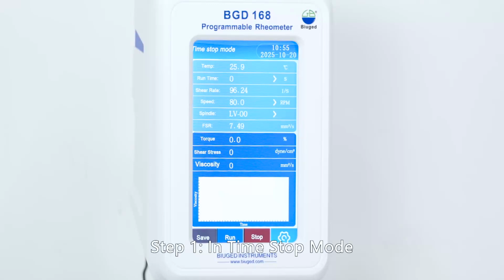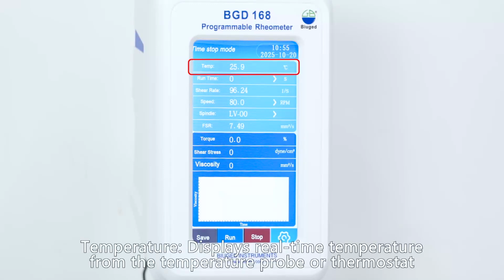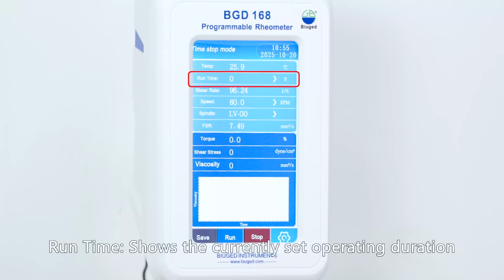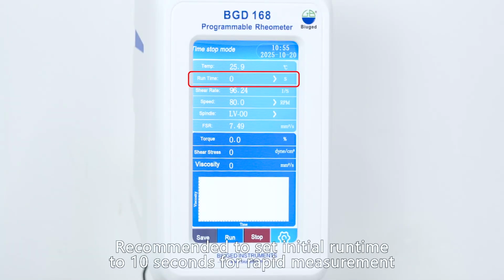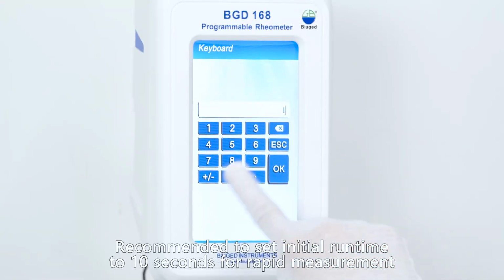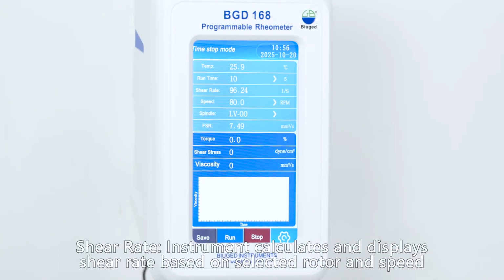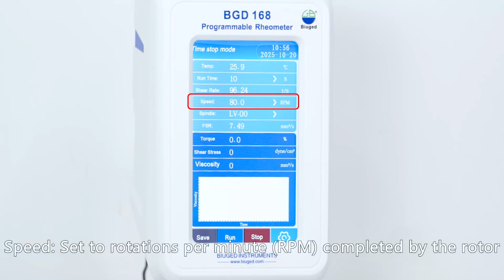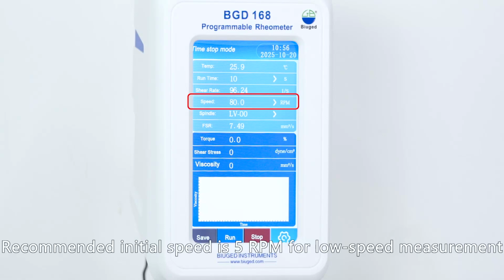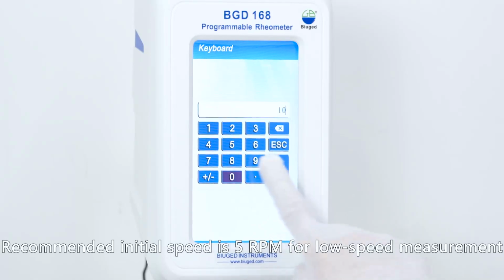Start measurement. Step 1. In time-stop mode. Temperature displays real-time temperature from the temperature probe or thermostat. Runtime shows the currently set operating duration. Recommended to set initial runtime to 10 seconds for rapid measurement. Shear rate. Instrument calculates and displays shear rate based on selected rotor and speed. Speed, set to rotations per minute, RPM, completed by the rotor. Recommended initial speed is 10 revolutions per minute for low-speed measurement.